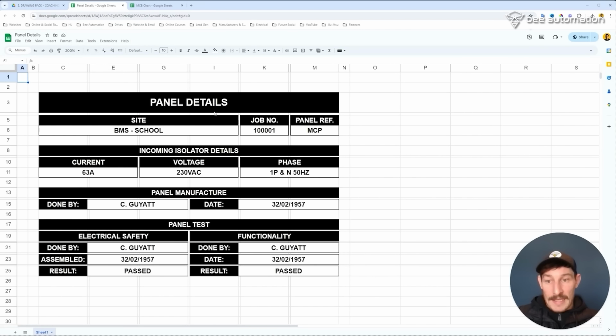For the panel details, it's pretty self-explanatory. What I've got is the site, the job number, the panel reference. In this case, it's a mechanical control panel, and there's only one of them. The incoming isolator details: the main isolator switch is up to 63 amps, 230 volt AC, single phase neutral, 50 hertz. Details of the panel manufacturer, so me, and the date.